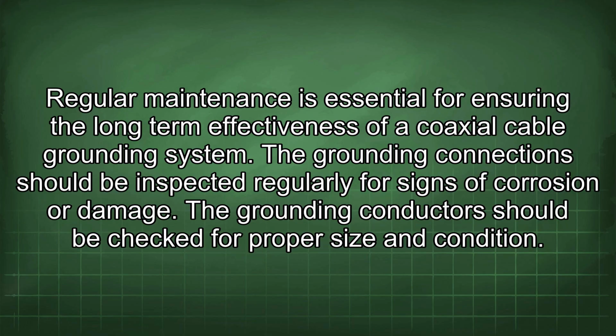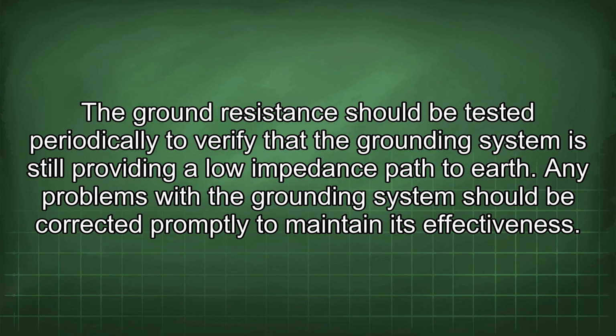Regular maintenance is essential for ensuring the long-term effectiveness of a coaxial cable grounding system. The grounding connection should be inspected regularly for signs of corrosion or damage. The grounding conductor should be checked for proper size and condition. The ground resistance should be tested periodically to verify that the grounding system is still providing a low impedance path to earth. Any problems with the grounding system should be corrected promptly to maintain its effectiveness.